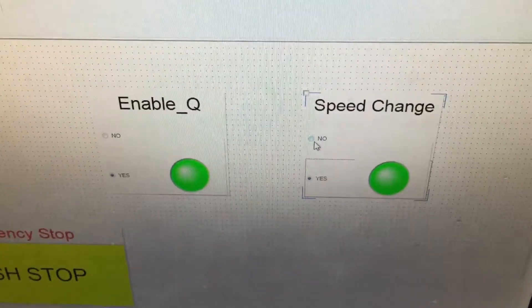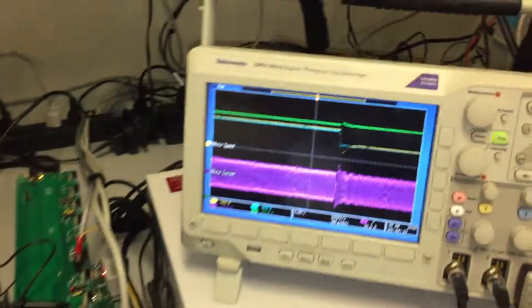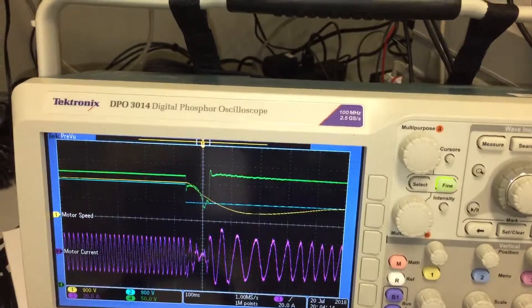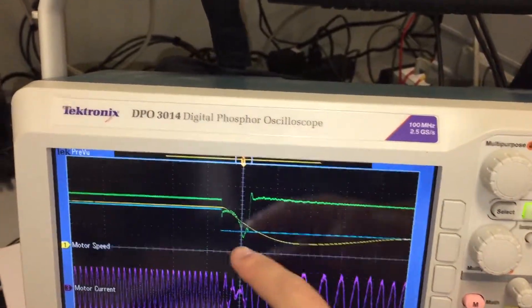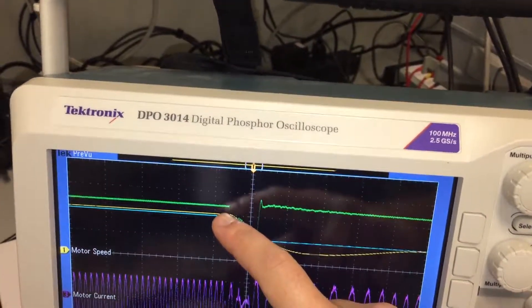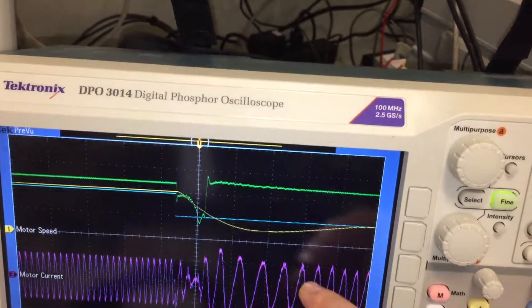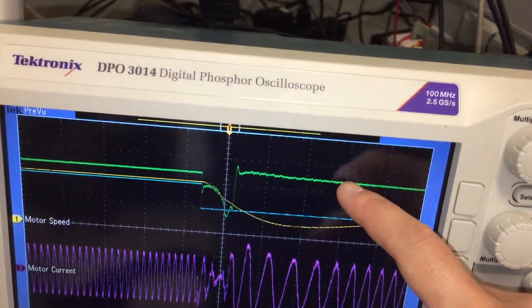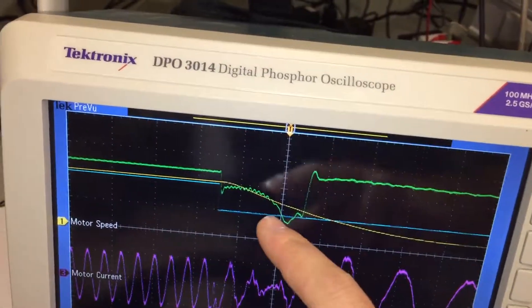I can decrease the motor speed using this button — the motor speed has now been reduced by half. On the oscilloscope, the motor speed signal is reducing from 1800 rpm to 900 rpm. You can also see the motor current signal and the floating capacitor voltage signal, which shows some transient during the speed change.